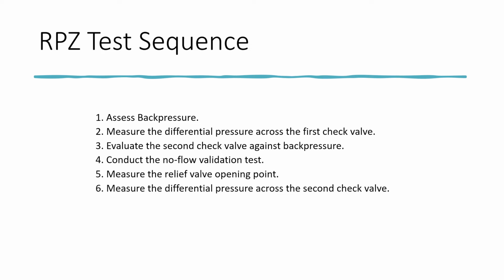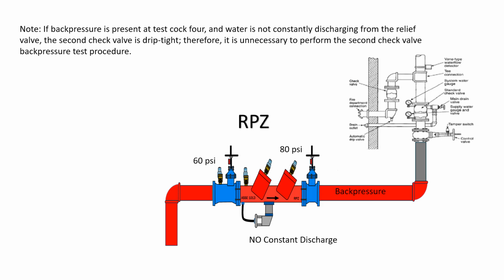RPZ test sequence. 1. Assess backpressure. 2. Measure the differential pressure across the first check valve. 3. Evaluate the second check valve against backpressure. 4. Conduct the no-flow validation test. 5. Measure the relief valve opening point. 6. Measure the differential pressure across the second check valve. Note: if backpressure is present at test cock 4, and water is not constantly discharging from the relief valve, the second check valve is drip tight.